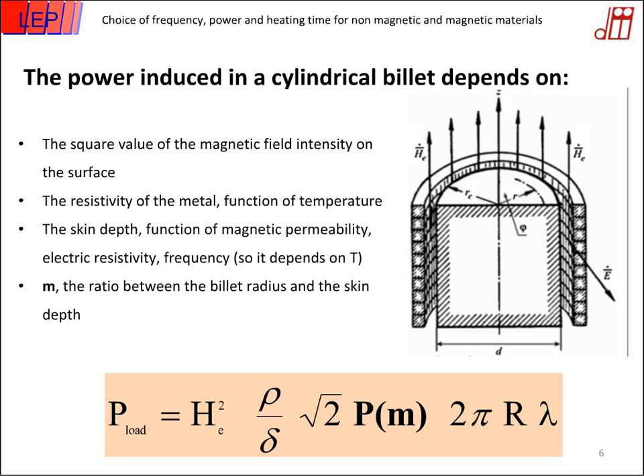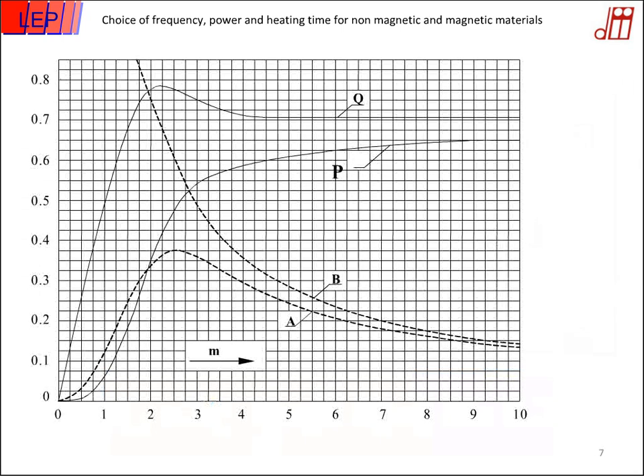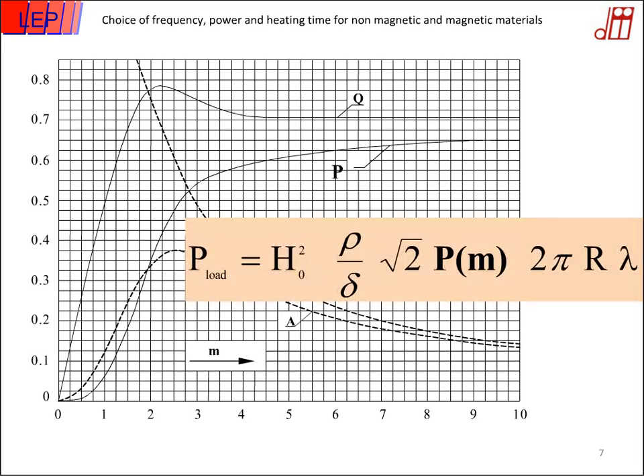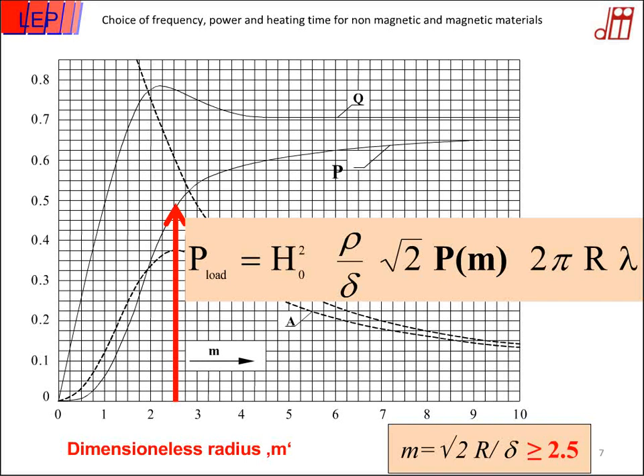Dimensionless quantities are very useful for a general description of this kind of process. In particular, the induced power depends on a parameter P that is a function of this ratio M. In the graphic, we have the value of P directly linked to the power we can transfer to the billet. We want to maximize that power, which means the M parameter must be at least 2.5 or 3. If this value is smaller than 3, we have bad coupling between the inductor and the billet.